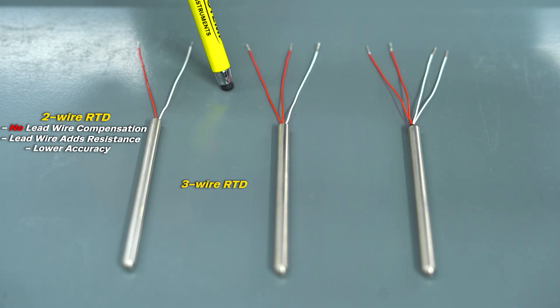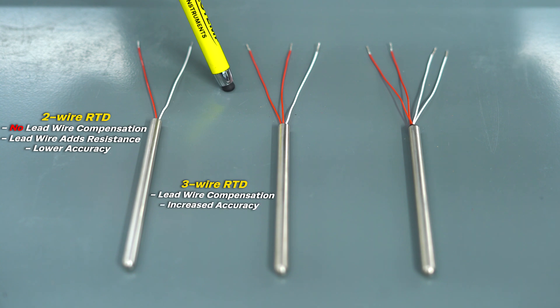A three wire RTD has a redundant lead wire on one side. This extra wire is used to measure how much resistance the wire itself is creating and then subtracts that resistance so that you're only measuring the resistance of the RTD element. This is the most common configuration for industrial applications and provides adequate compensation for lead wire resistance.